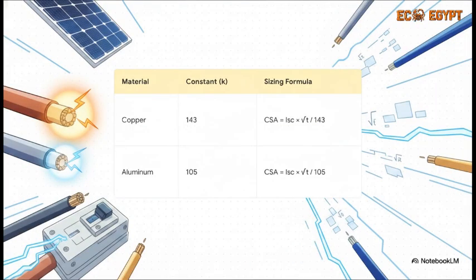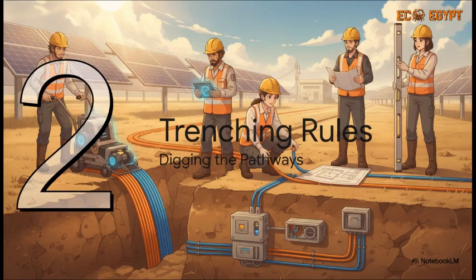And that brings us to the third check: short-circuit thermal survival. Basically, if a massive fault happens, the cable has to survive an intense thermal spike for the fraction of a second it takes the breaker to trip. Check out how the math changes based on your conductor material here. Engineers use a constant, denoted as K, of 143 for copper and a much lower 105 for aluminum to calculate the minimum safe cross-sectional area. It proves that even during a worst-case electrical fault, your cable won't literally vaporize before the safety systems can kick in. Moving right along to Section 2, trenching and installation rules, digging the pathways.